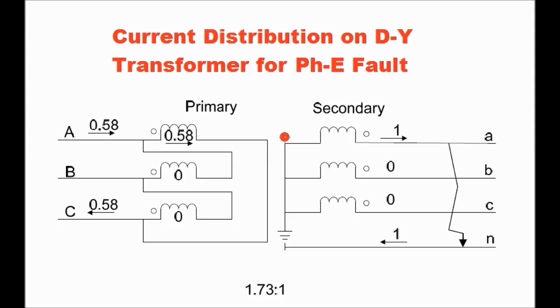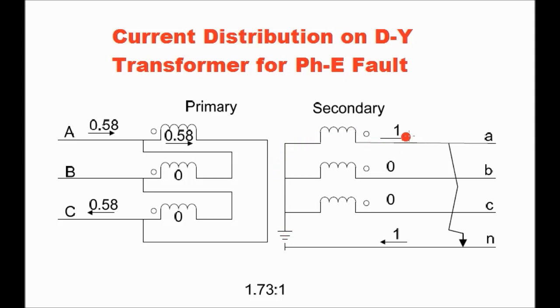The next case study is fault current distribution in a delta-star transformer for a single-phase to earth fault occurring in the star side. Let us consider a single-phase to earth fault in the red phase, and for ease of calculation let the fault current be 1 ampere. So 1 ampere flows in the red phase winding toward the fault point, goes to ground, flows back through the neutral which is grounded to earth, and returns to the red phase winding.